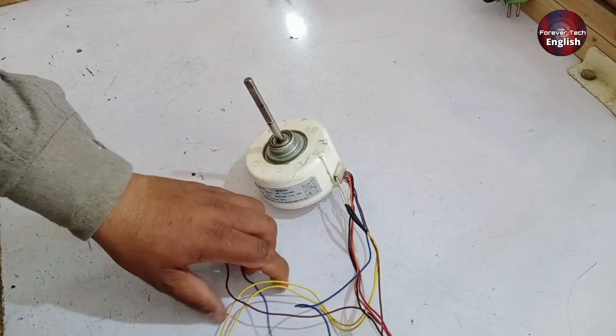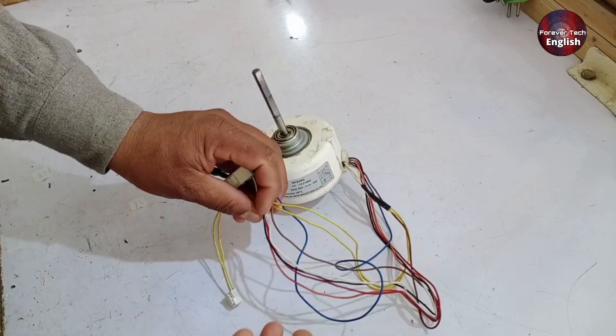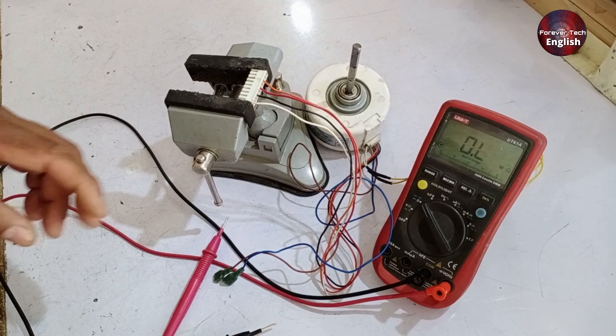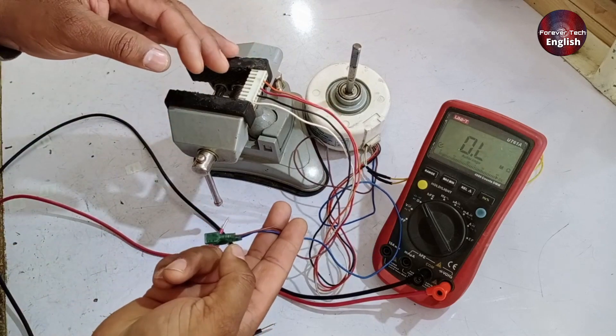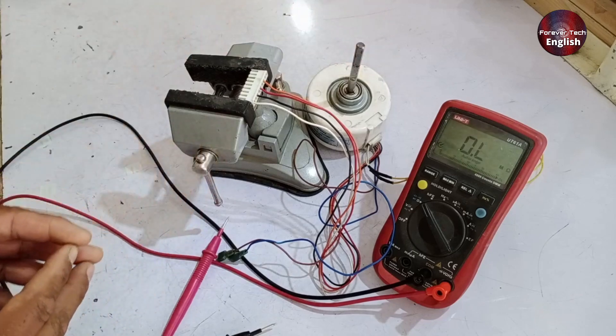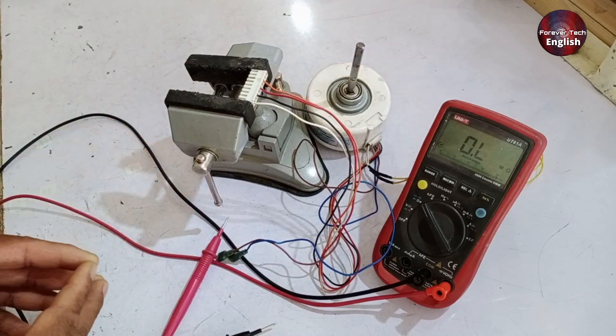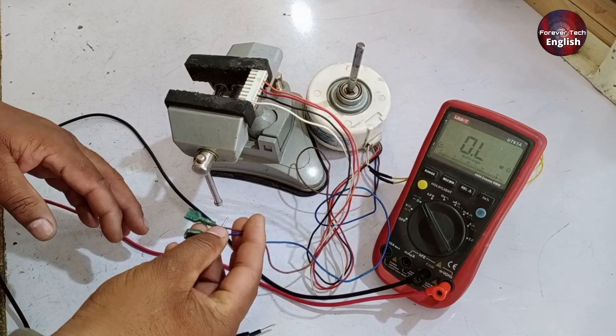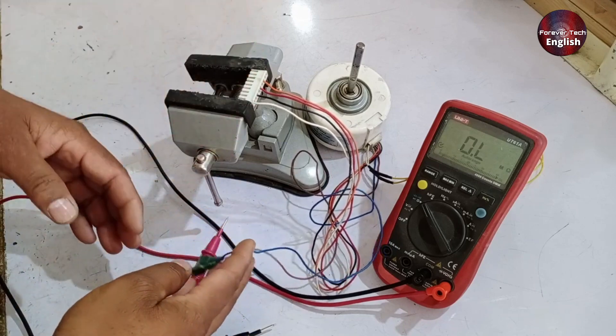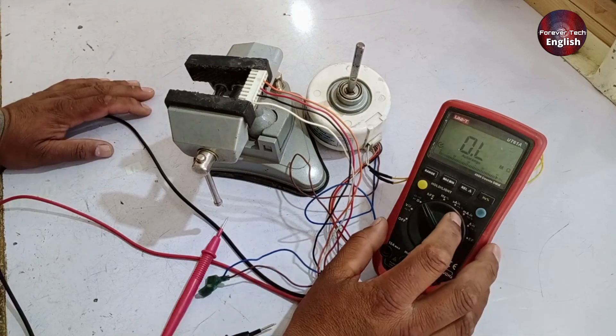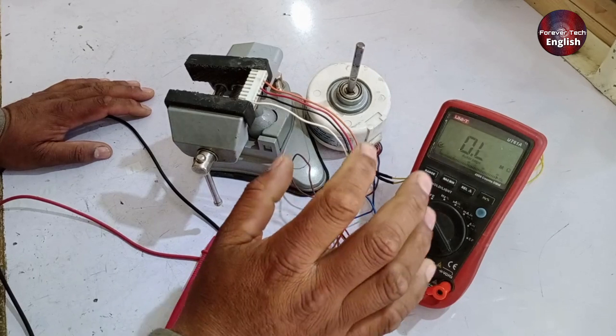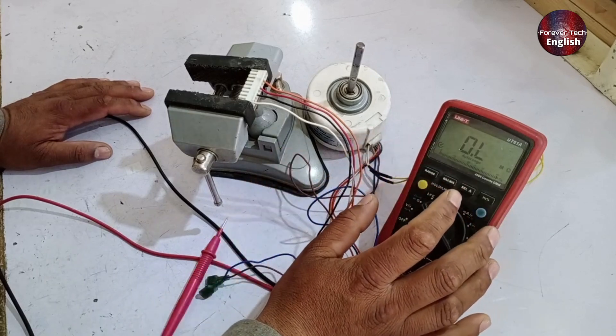To understand the windings, you'll need to test them with a multimeter or a series board. The company has brought out six wires from this motor. Even if there were only five wires, the same functions could still be achieved. However, since there are six wires, we need to figure out what the remaining wires are for. The company has made two wires common at one point, so we need to identify which ones are common. For that, you'll need a multimeter. You can set the multimeter to continuity mode or check in ohms mode, but continuity mode is easier if you are less experienced.